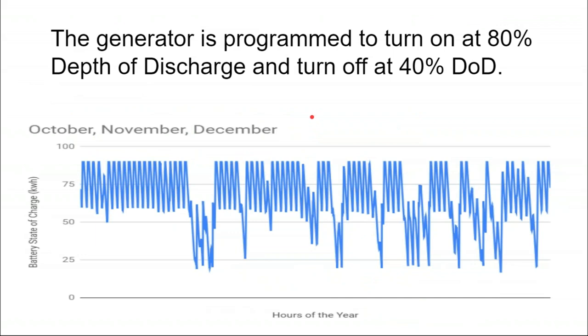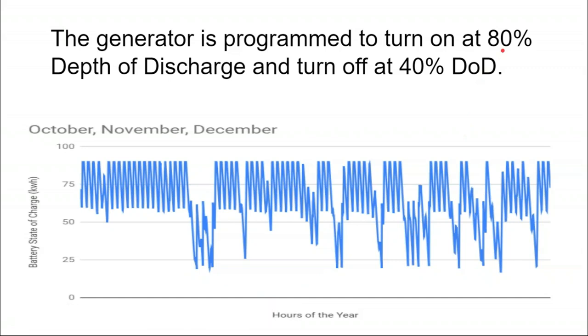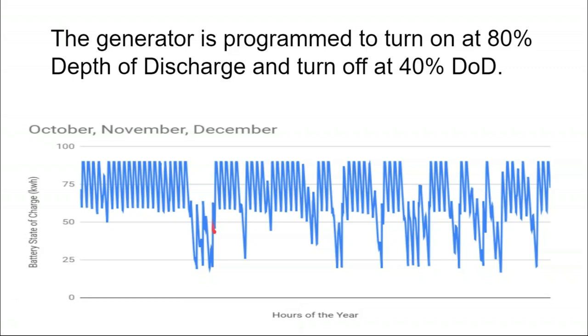So at that point, you say, okay, if I have a 90 kilowatt hour battery bank, I know my generator turns on at 20% depth of discharge. If it turns on, we're not going to wait for the next sunny day to recharge the battery, we're just going to charge it all the way to the top. Or you could say, no, we'll charge it up to 80% range, and then the sunny day comes and the generator drives it to the top, then it competes with solar for the next few days, then maybe the generator drives it to the top again, and finally a sunny day brings it all the way up to where it should be.